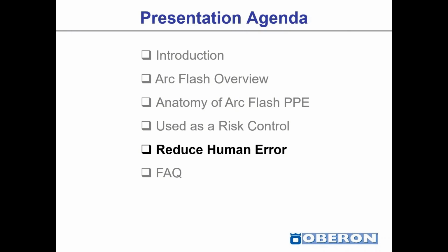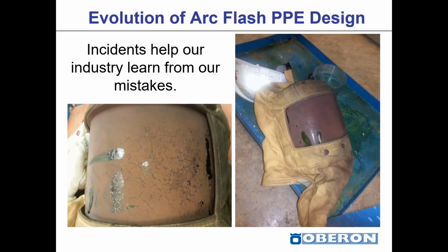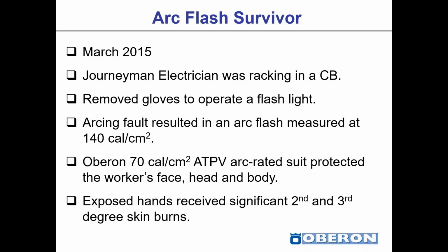And now reducing human error through the innovation in the arc flash PPE. So evolution of PPE design through our evaluation, our assessment of incidents within industry, that's what we've used to help learn from our mistakes. And what I mean by that is, here's one example from Canada, from Saskatchewan actually. So this happened in March 2015. This worker was racking in a circuit breaker. In this work task, they removed their gloves to operate a flashlight. And what occurred, Murphy's Law has it, if you take off part of your PPE, you're going to be involved in an arc flash. And in this situation, the arcing fault resulted in an arc flash measured at 140 calories. This worker had on a 70-calorie arc flash suit, which gave them protection for their face, their head, their body. However, the exposed hands received significant second and third degree skin burns.